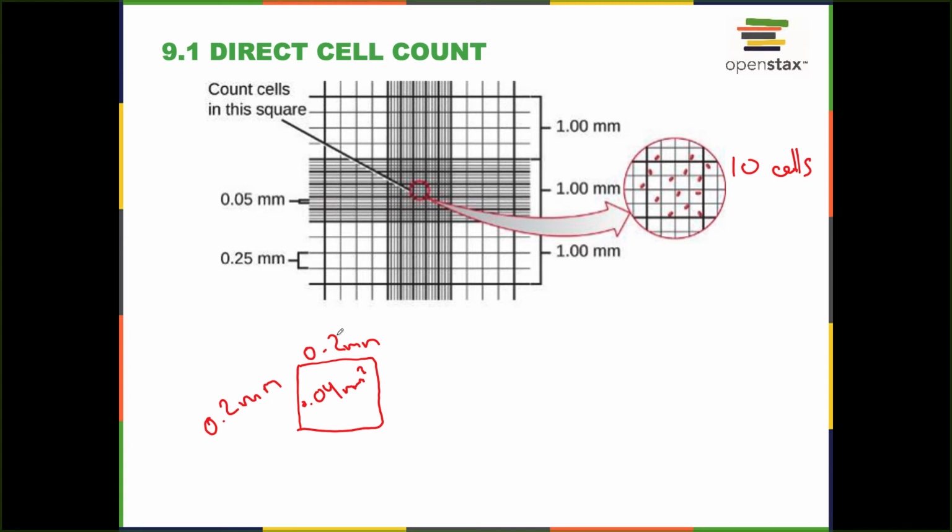Now, this chamber, it's not included in the data here, but they'll always tell you about the depth. So the depth of the chamber is 0.2 millimeters. That means the chamber is the space between the actual cells and the cover slip. So if we look at it from the side, here's our cover slip. This here is 0.2 millimeters. And every single one that you see is going to be calibrated. I'm going to double check this number because it wasn't written down. Okay, so that's correct, 0.2.